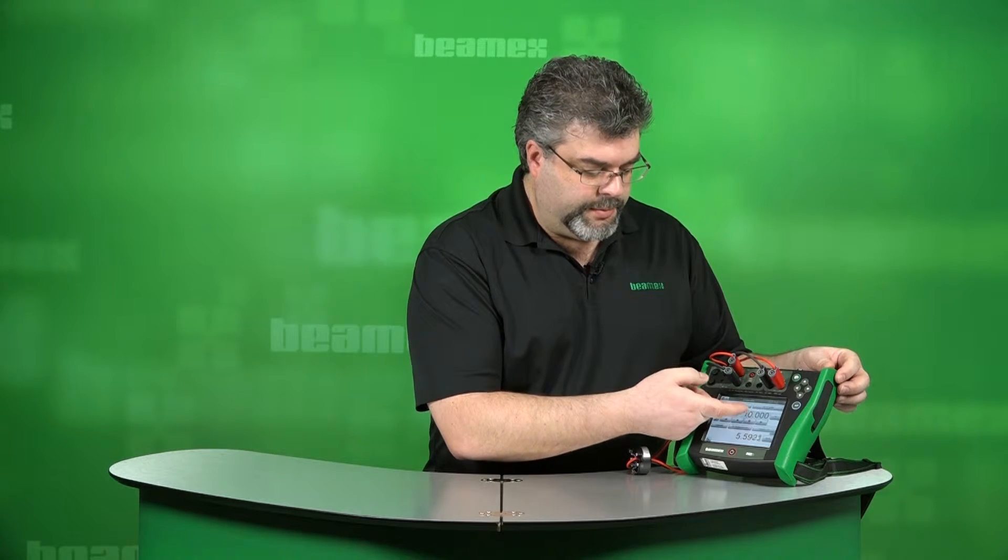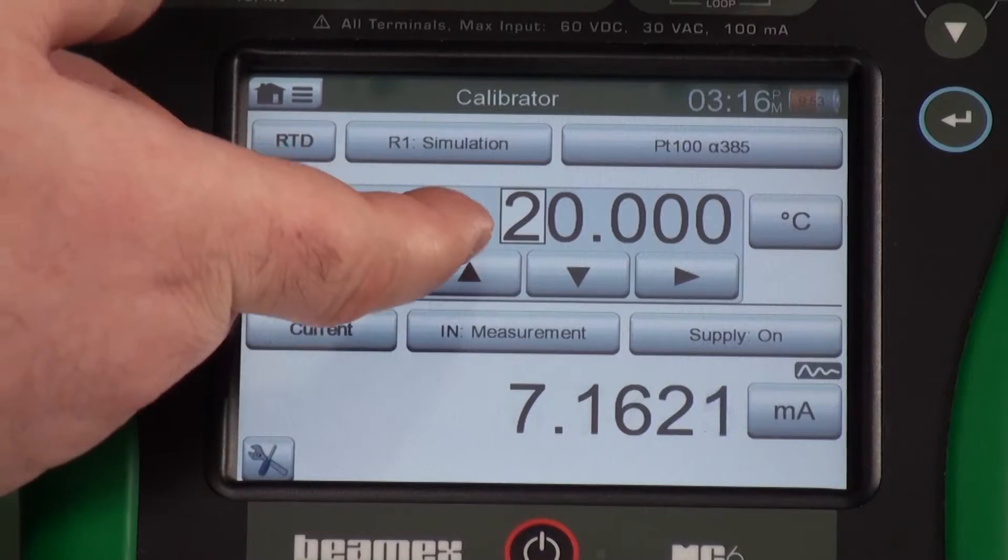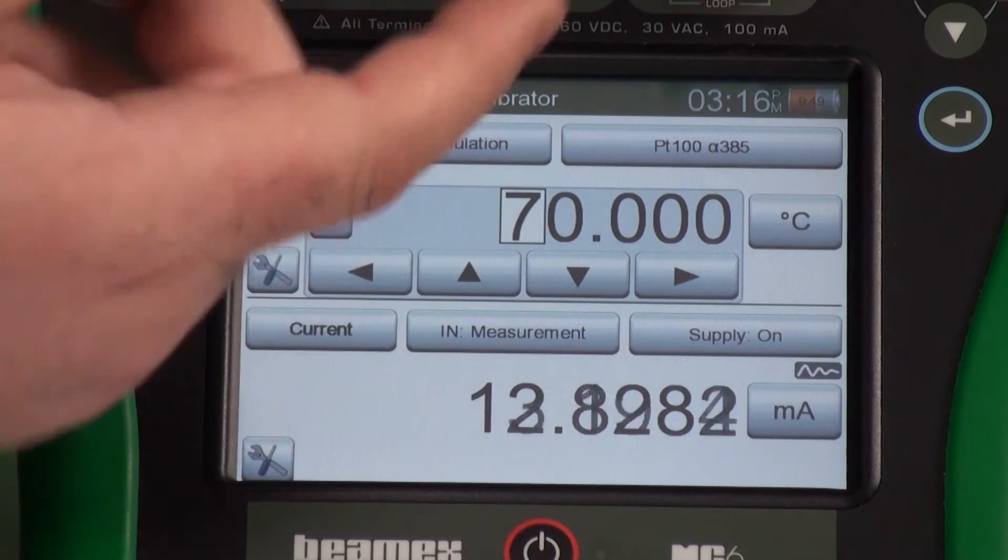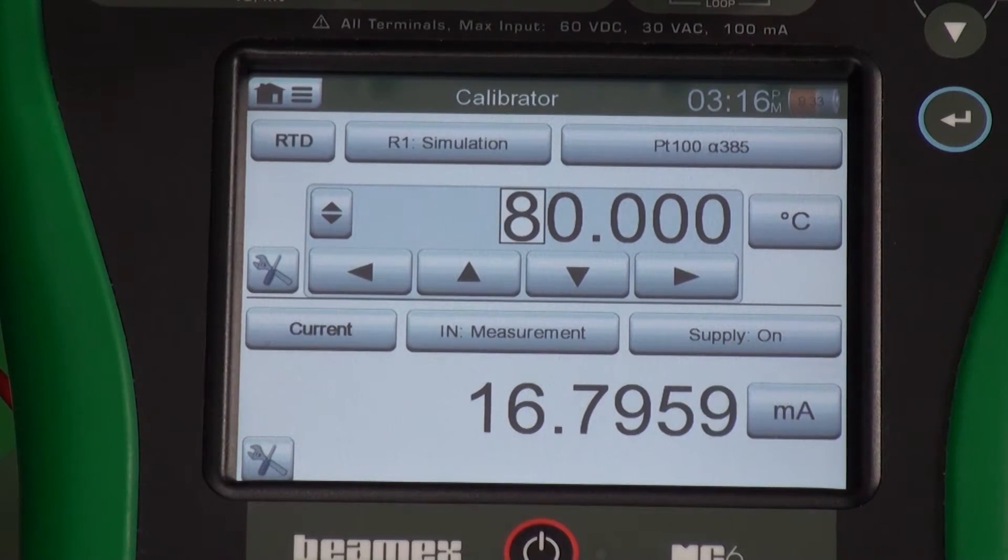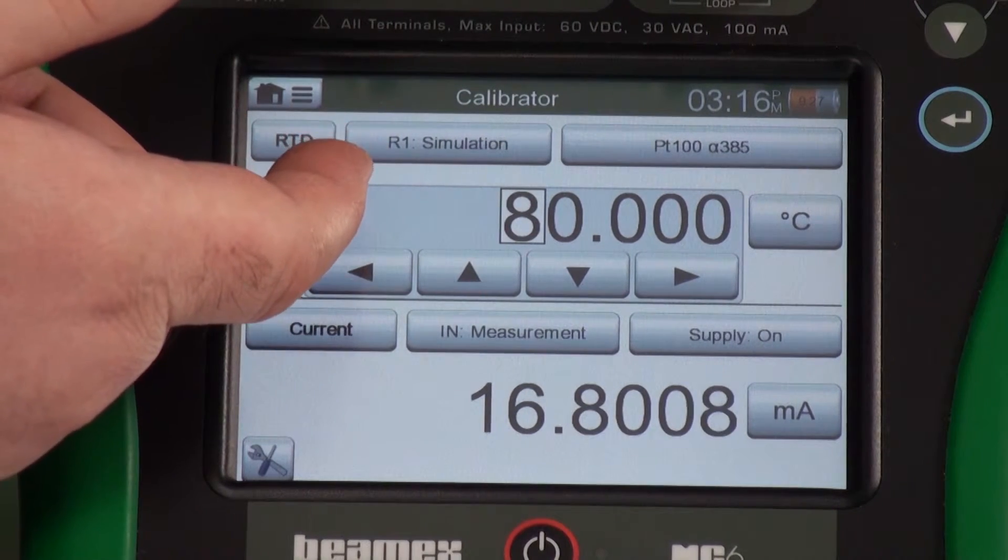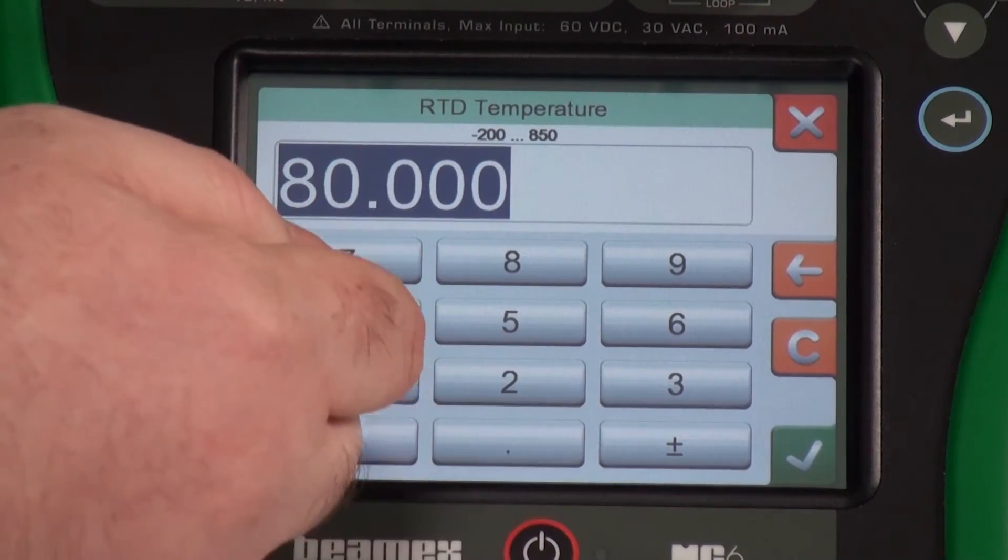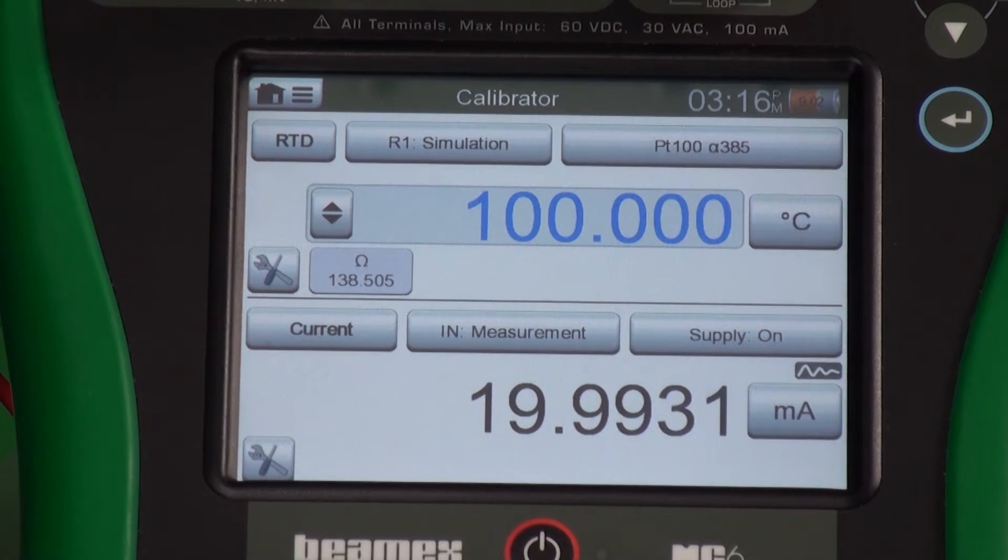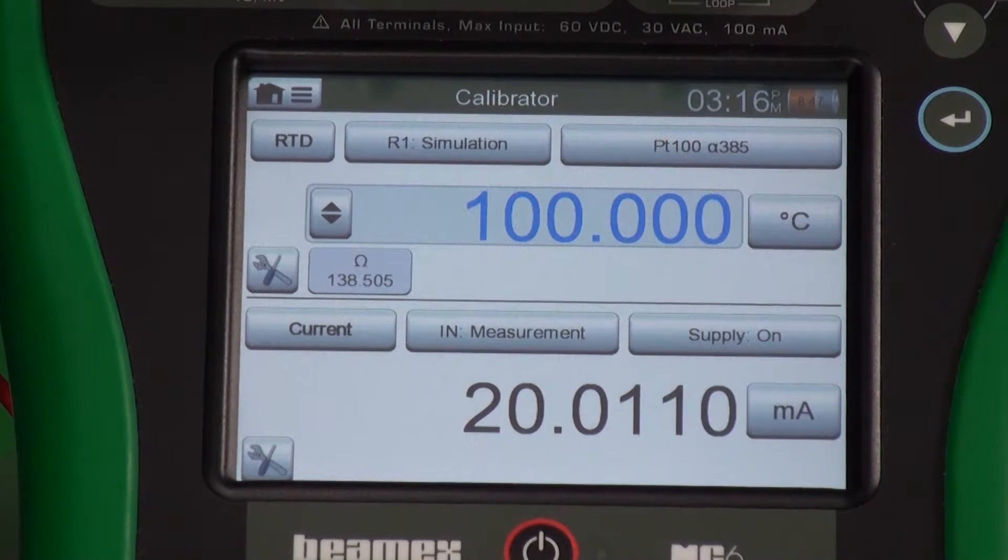I could use this. Let me move over and I'll just start increasing my temperature until I get 20 milliamps out. Now I could use this roller method or the nudge method or I could simply type in a value. Maybe I want 100. So now we've entered 100 degrees and we have 20 milliamps out. So now we know our range is 0 to 100.